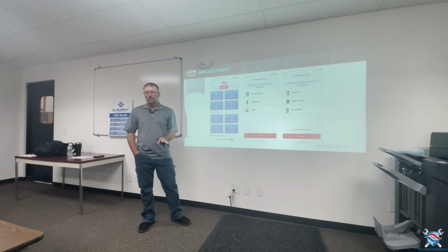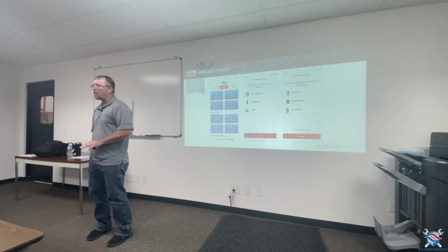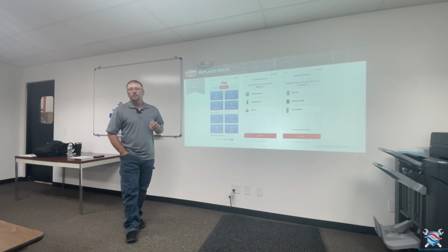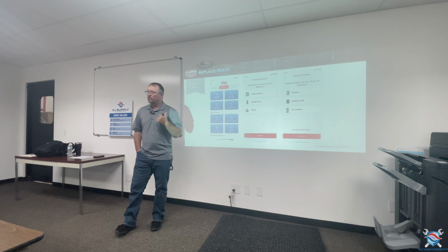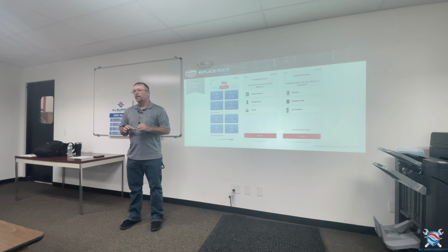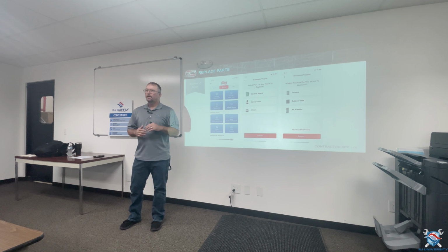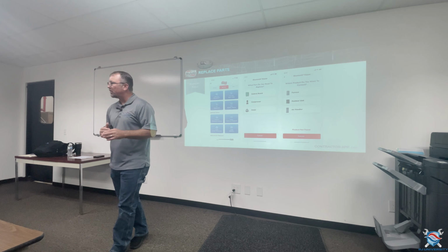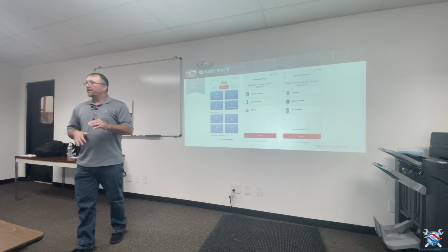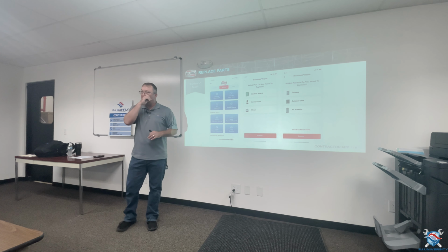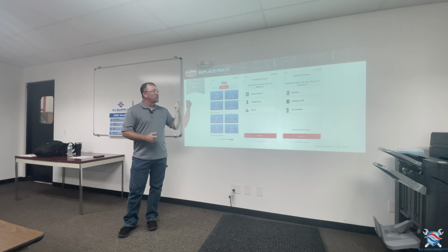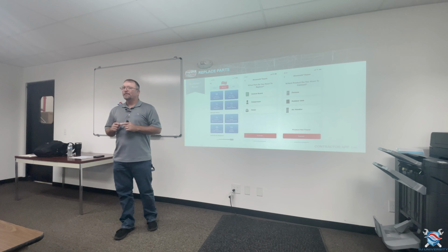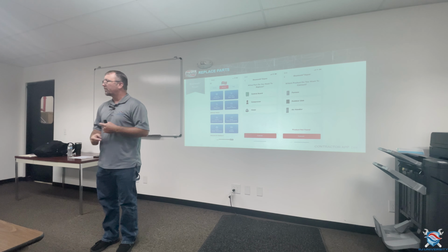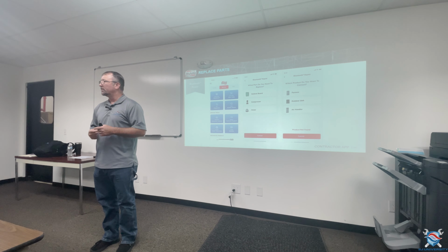Motors, one thing I want to touch on motors, I've run into this a few times and I don't know why. On the new outdoor units that are using the ECM motors that are programmed through the board, what I've run into is, for whatever reason, they seem to be losing connectivity with the board. So it'll give you a condenser fan motor fault. What you have to do in that situation, it's truly not a bad fan motor, is you have to go through the service and repair and basically act like you're putting a brand new fan motor in there and reflash the fan motor to the control board.